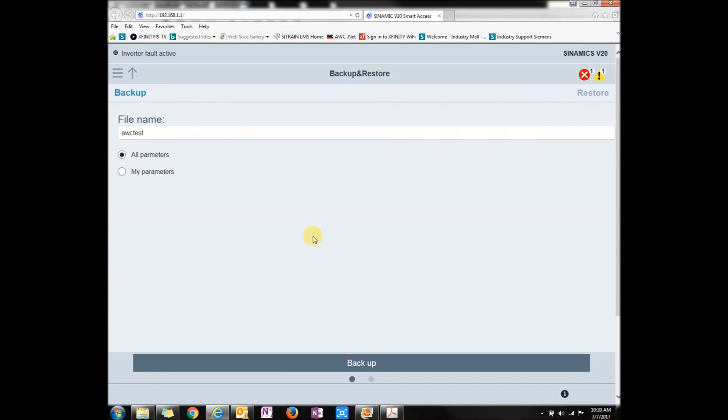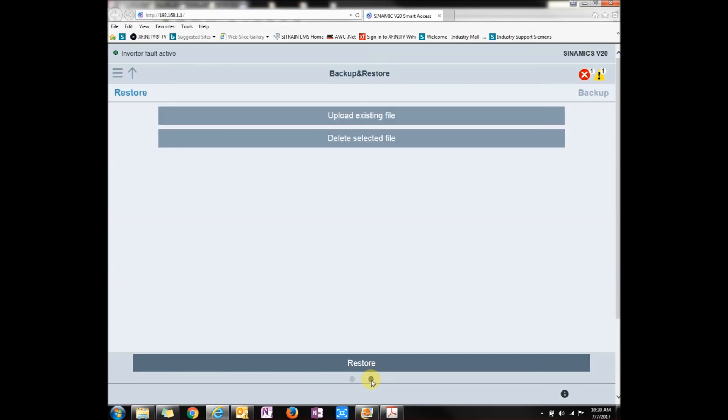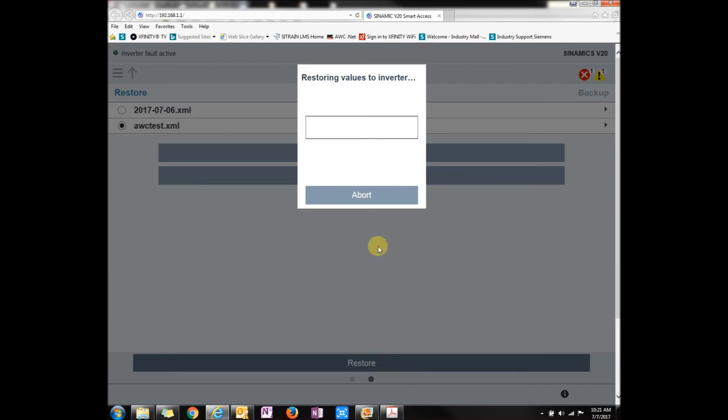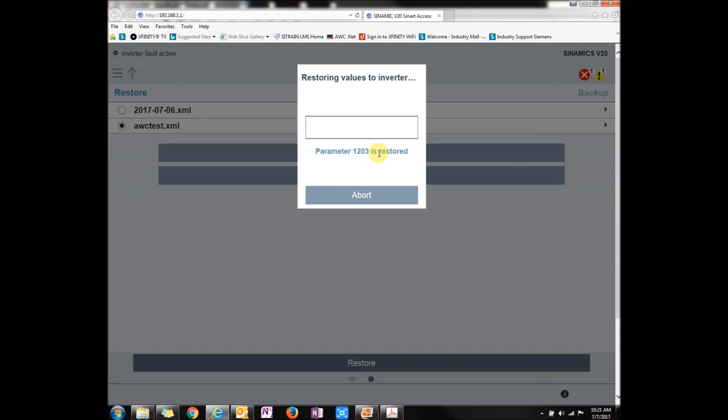I haven't figured out how many files it saves to it. I need to research that a little bit. But I'm just trying to get this Smart Access module out so y'all can see it. Now if you go down here on this second dot, that's where you would restore to the drive. See? AWC test. And this is one I did with Elizabeth Harris. It's still on there, and she did it with her cell phone. So that's why I don't really know if it's saved on the module. If I go to AWC test and press restore, it's now transferring all the parameters that was on the drive back to it. This is one good thing. If you have multiple drives doing the same thing, you could back it up, then restore it to five different drives. It's going to be the exact same as long as it's the exact same configuration.